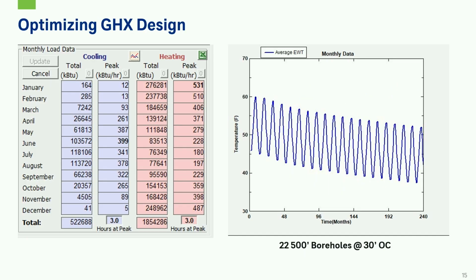Great. Okay, so like we've been stressing, the energy loads are the most important aspect of the ground heat exchanger design. What my geotech engineer was saying was that if you have garbage energy loads in, you're going to have garbage GLD results out. So you really want to make sure that your energy loads are representative of what's happening in the building, and you're taking into account all the energy efficiency measures and things like that. We were actually looking at a situation where there were extremely imbalanced loads. We were just playing around at this point, and we weren't getting results even if we put in an obnoxious amount of boreholes for just an individual building because the imbalance of the loads was so high.